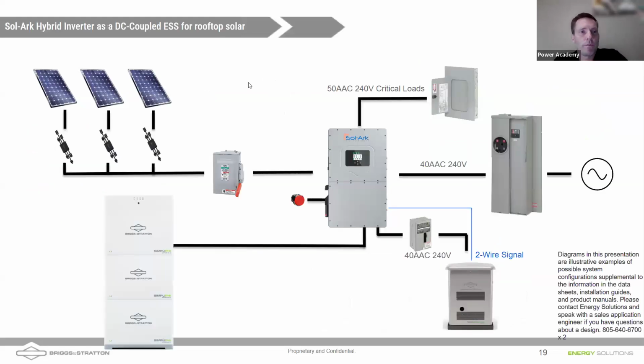Here's an example of a hybrid inverter that's DC coupled. So we've got solar panels coming in. These are not microinverters here. These are rapid shutdown devices. Those are APsmart, Daniel? Yeah, and those actually can connect up 2 modules per device. They do singles as well. Yep. And an alternative popular brand is the Tigos, right? I don't show a transmitter on here, but an external transmitter is required for the Tigos. And depending on how big your solar array is, you might need more than one transmitter for your system.